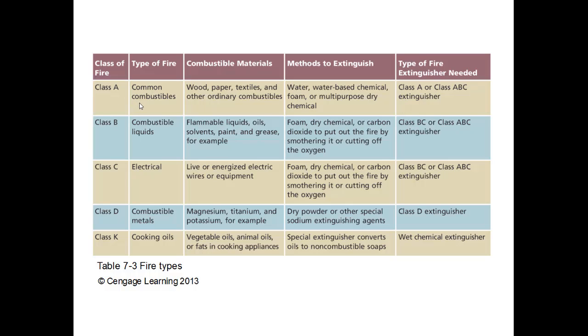Common combustibles would be a Class A fire — paper, wood, textiles — extinguished with water, foam, or dry chemical. A Class B fire involves combustible liquids such as oils, solvents, paints, or grease, requiring foam, dry chemical, or carbon dioxide. This is why you should never put water on a grease fire — it expands the fire and makes it much worse.